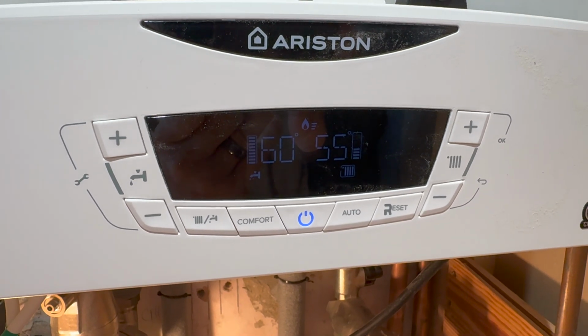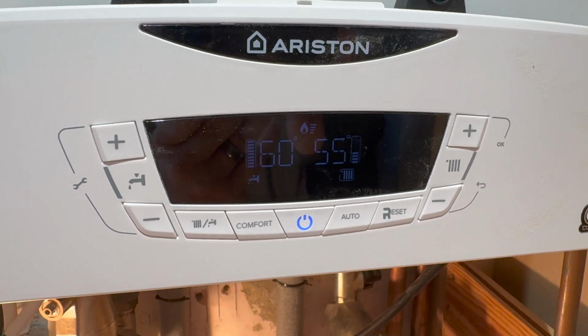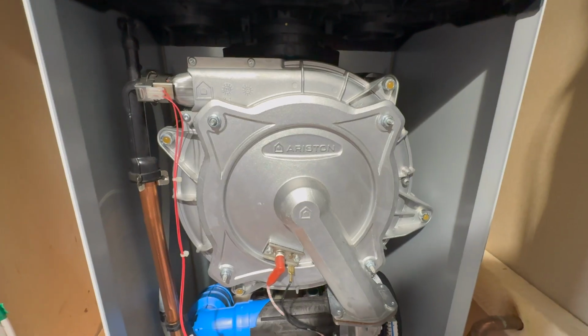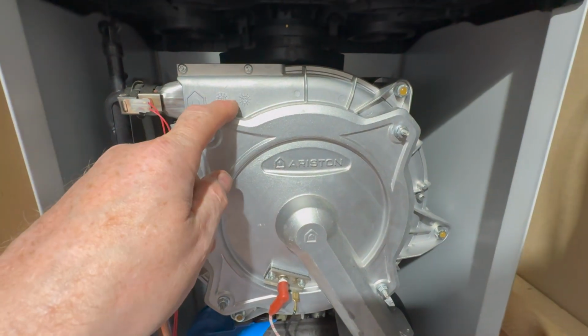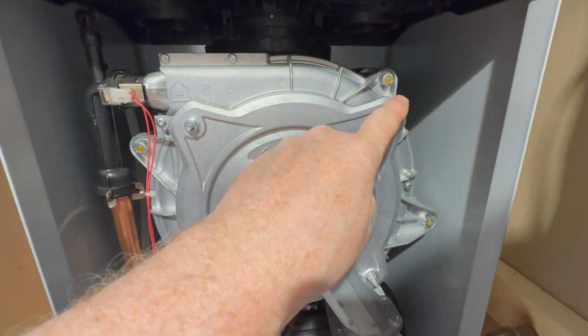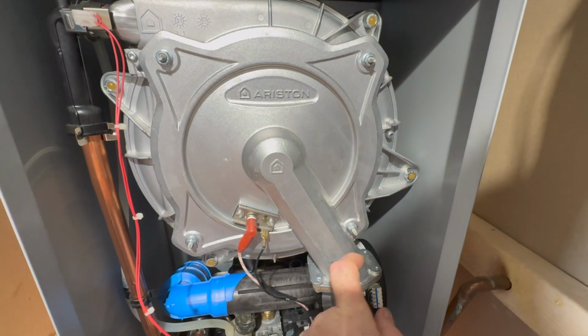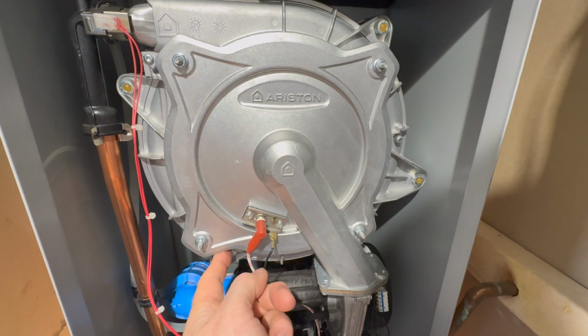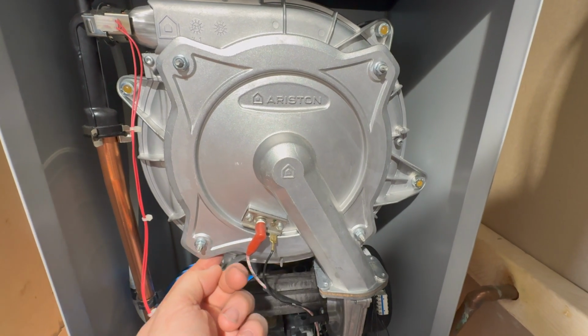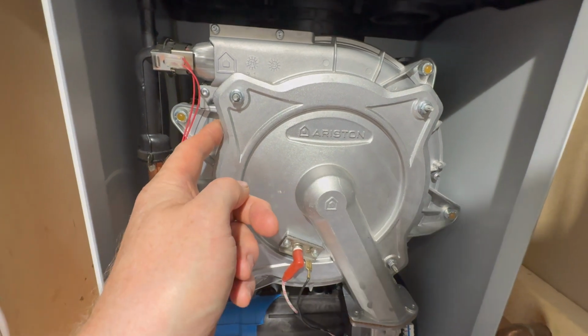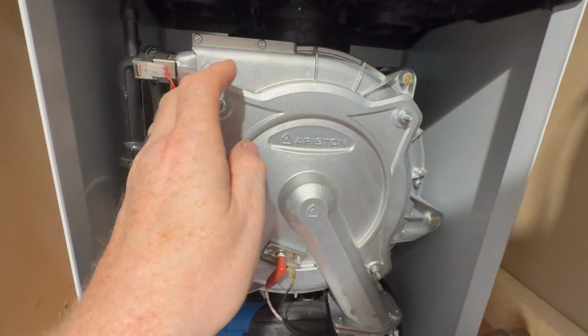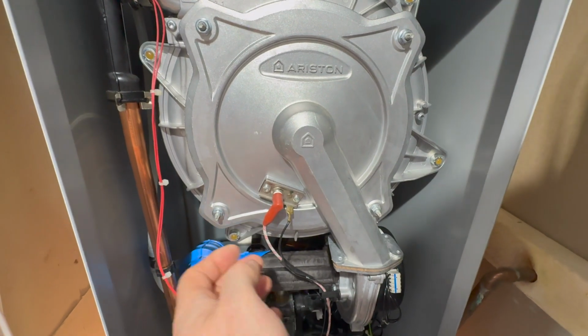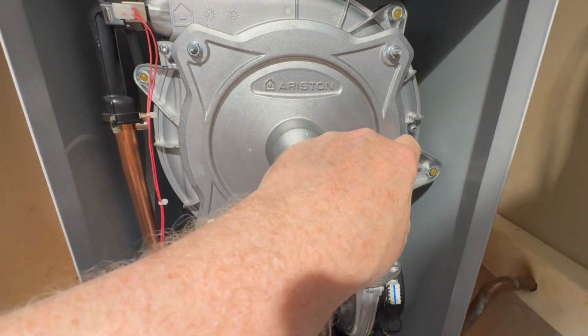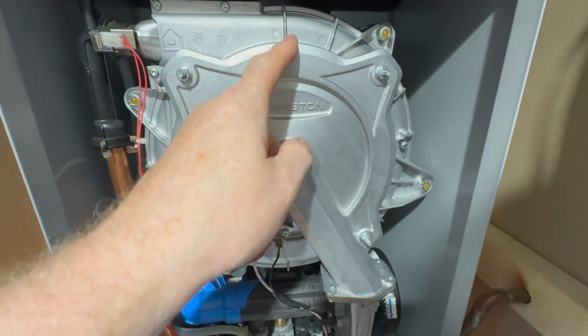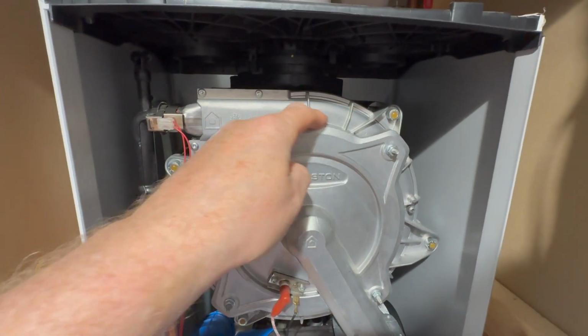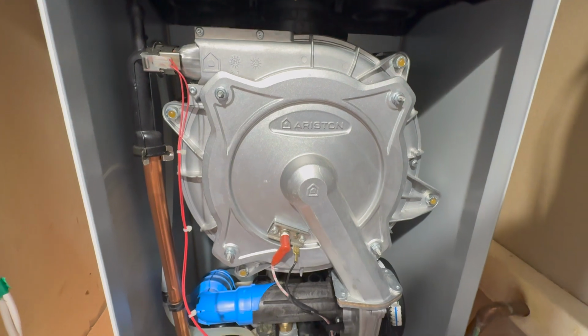And there it goes. And it seems to be a little bit quieter than it was before. Now the boiler is up and running for the first time, what I like to do is run my finger around the combustion door to make sure it's not leaking any products of combustion. I'm also going to be doing a sweep test around here, but this is always my first go-to test, because if this was leaking there would be hot flue gases coming out of here and it would burn my little pinky. So that seems to be pretty good.